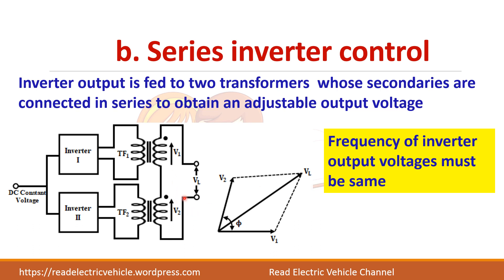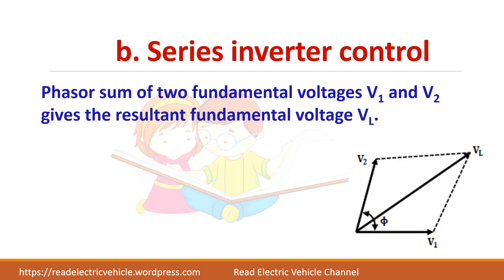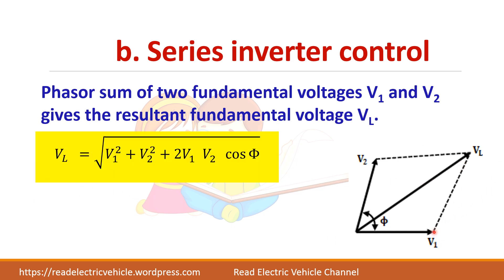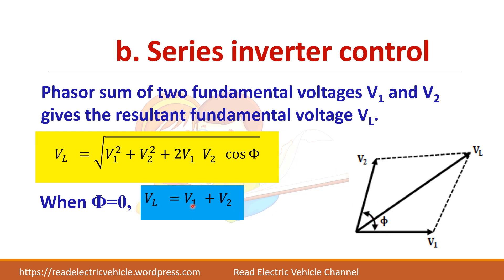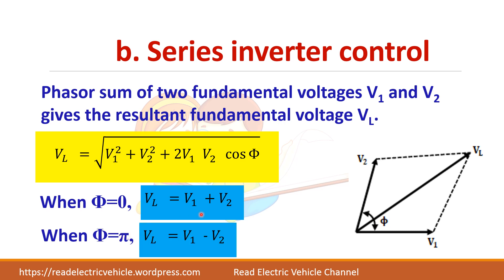The only problem in this method is that the frequency of the inverter outputs V1 and V2 should be the same so that you can add them. The phasor sum gives the resultant voltage: VL = √(V1² + V2² + 2·V1·V2·cos φ). When φ = 0, VL = V1 + V2. When φ = 180°, VL = V1 − V2, and when both magnitudes are equal the resultant voltage becomes zero.